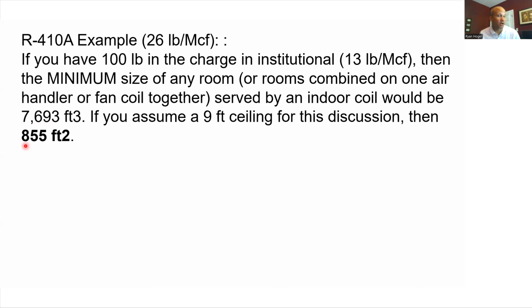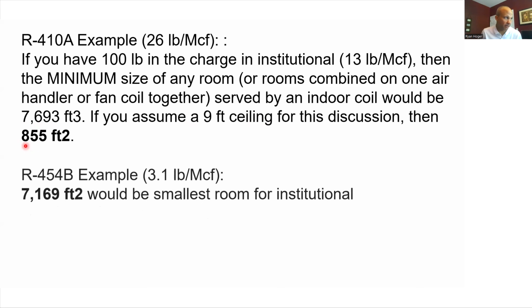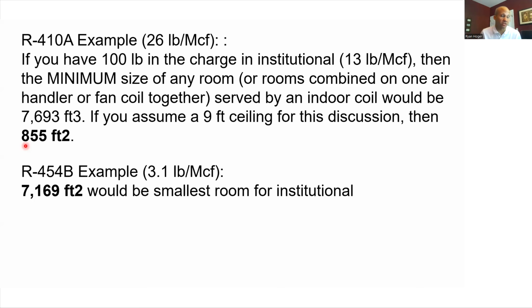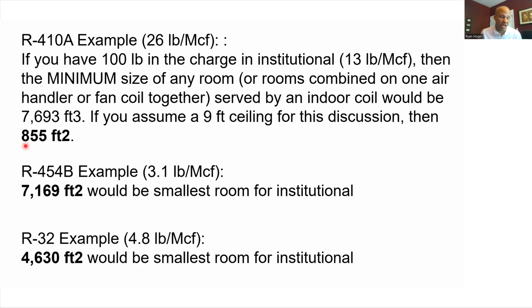This engineer wanted to know what would happen if he switched to A2L refrigerants because his project timeline gets pushed out. So with R-454B, the smallest zone would have to be 7,000 square feet, which in fact was the whole building, which means it would be a useless thing. We couldn't use R-454B, and R-32 did not do us any favors. So we really couldn't even do the project with these A2L refrigerants. This is why, on the deadlines, VRF gets an extra bonus year to figure things out versus the other split systems. They have to come up with another solution other than just doing it in order to be allowed to have this.